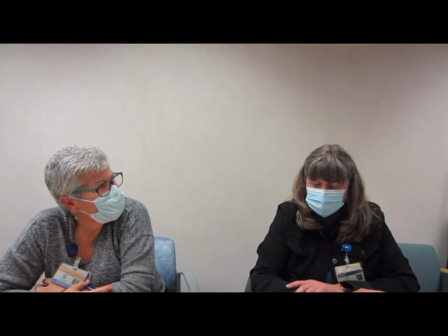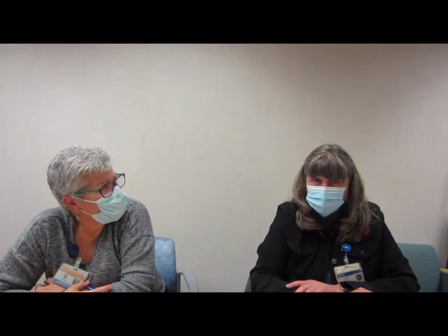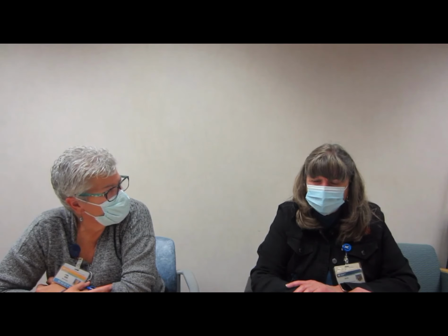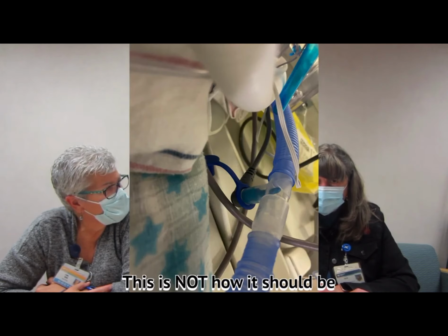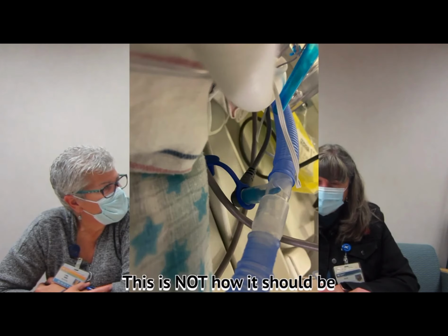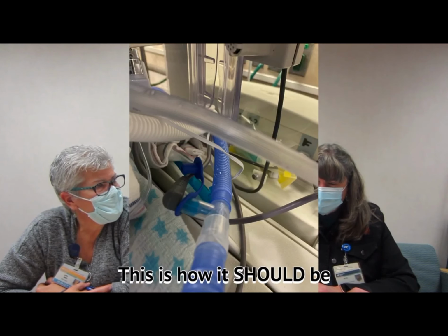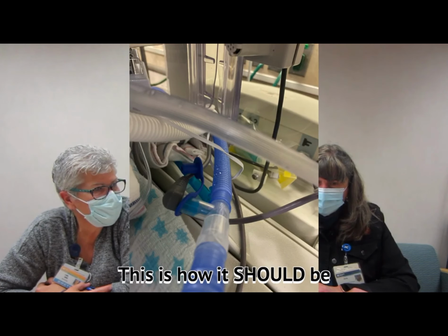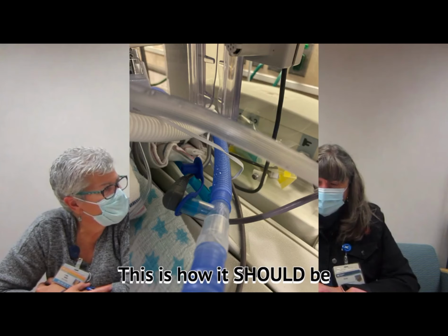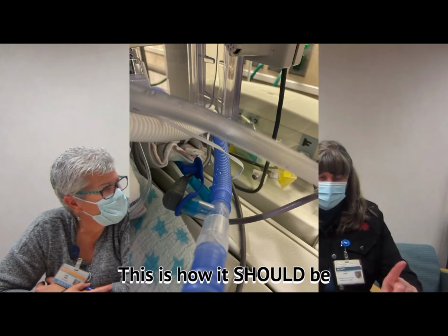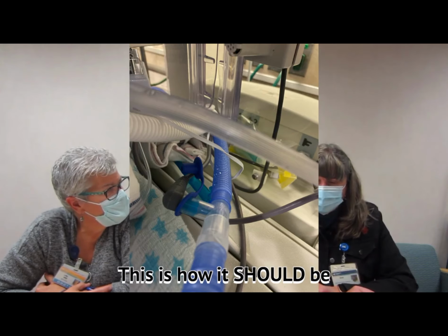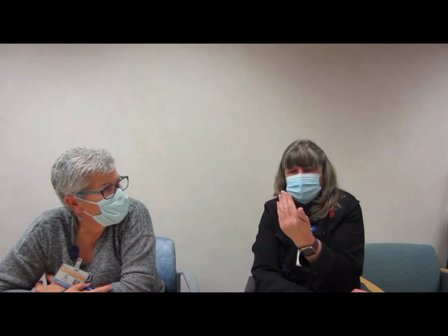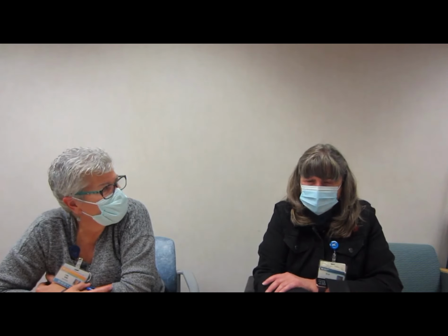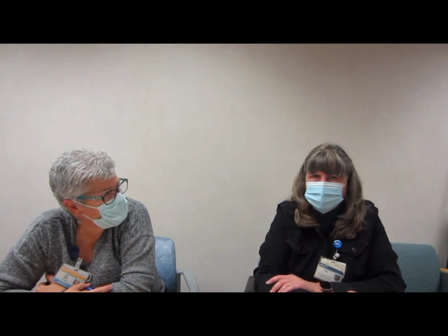The Fisher-Paykel heater works by two probes that the temperature is supposed to be balanced between them. If the probe closest to the baby is upside down and water sits on it, that's going to cool it off, and it's going to start heating itself higher to try and compensate for that, and you're going to get a ton of rain out. So whenever you reposition your baby, you should look at that probe, which is about 2 feet down from the baby in the blue circuit. It should be pointed down. If it's turned up like this, water's going to sit here and you're going to get a lot of rain out. So you should try and position it so it's always pointed down so water can't sit on it.